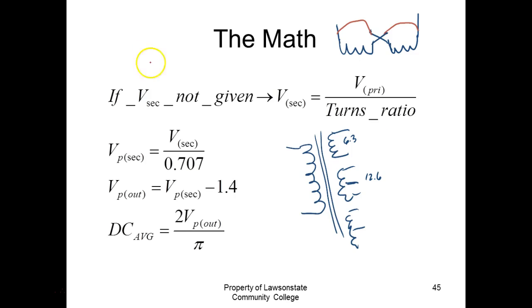Over there, all our devices are set to run on 120 volts, but I can run it off a 440 or 240 supply. We can either wire it to divide by 4, or wire it to divide by 2. Does that make sense? So we have multi-winding primaries, transformers that can be wired to run different primary voltages.